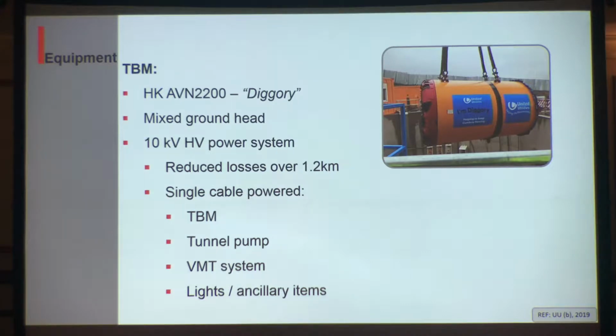The main reason for this is that by stepping the power up to that voltage, you have a smaller current flowing through the cables up to the TBM, meaning reduced power losses over the 1.2 kilometre length of cable. That enabled us to have a single power cable going up to the head of the TBM, powering the TBM itself, the first two tunnel pumps, and all the ancillary items up there - the VMT system, lights, and other small turret pumps in the tunnel.